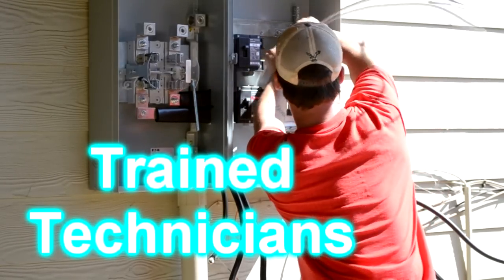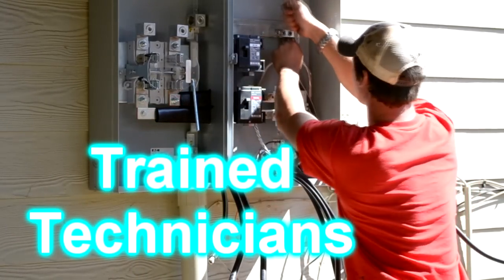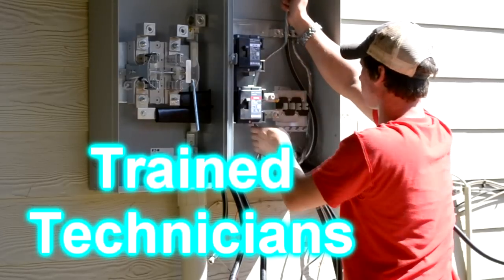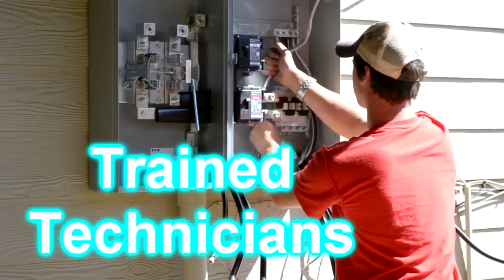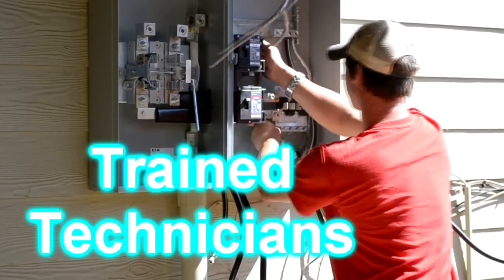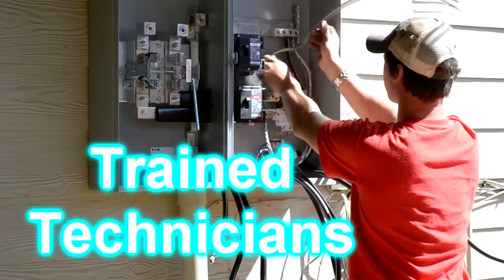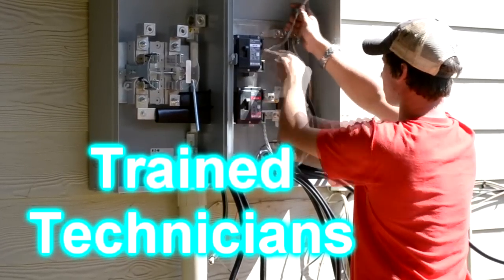Now Curtis is landing the ground and the neutral conductors into the neutral bar in the 400 amp load side of the service. He is also coating the aluminum wire with Noalox, which keeps it from corroding over time.